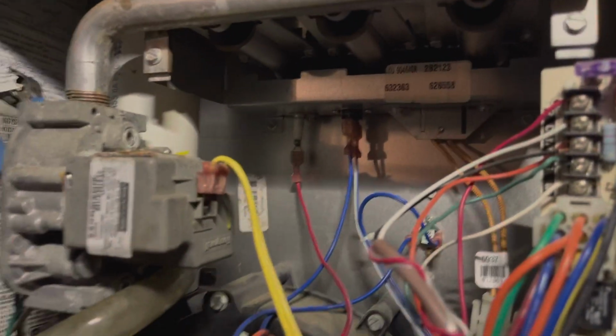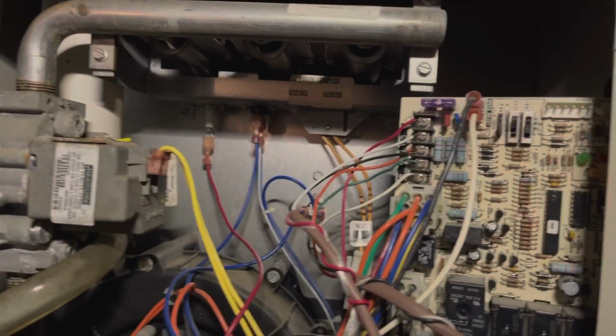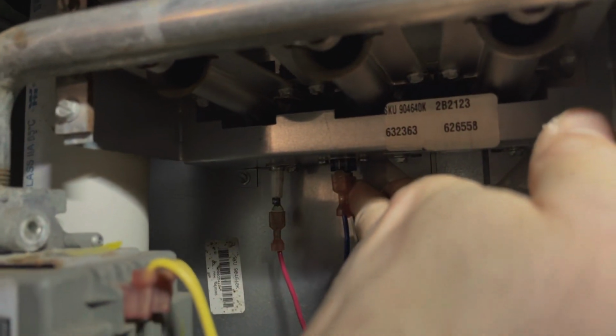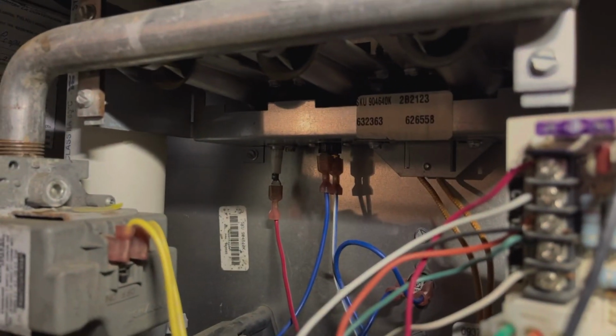So down to the bottom of it, our issue was this limit switch. So it tripped, and it actually has a button on it here to reset. So all said and done, I just clicked that button. I'll see if I can zoom in so you can see it.